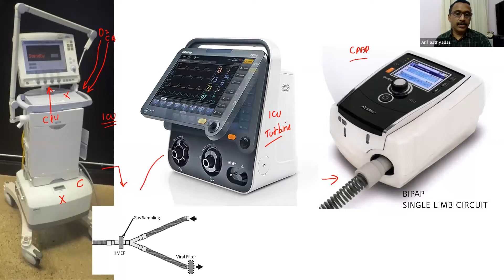The third type is your BiPAP or CPAP machine. Both look alike. The main difference is that this has only a single limb. The exhaled gases go out at the patient end. We'll see what modification we should make to the circuit when you're using this. For the other two ventilators, we use the dual limb circuit. Through one port, inspired gases go in, and through the other, the exhaled gases come out, which is measured by the ventilator before it's expelled. This is called the exhaled tidal volume.